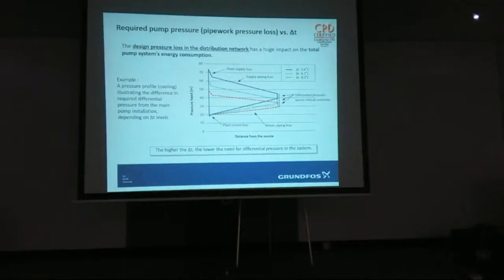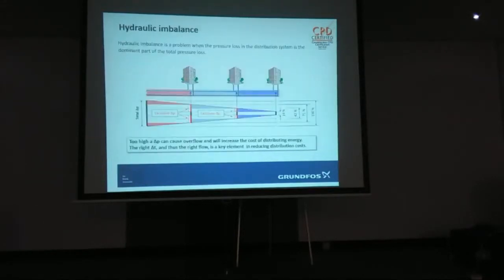Just about completely. But it's a pressure distribution diagram, done with different things. Here's a typical block of flats, very similar to what we've got out the back here, on the other side of the road. Energy centre, pumping out to 3 different blocks. As you go down the line, the first one could be 100 kPa, then you get into 70 kPa, here 42, whatever, at the very end 14.